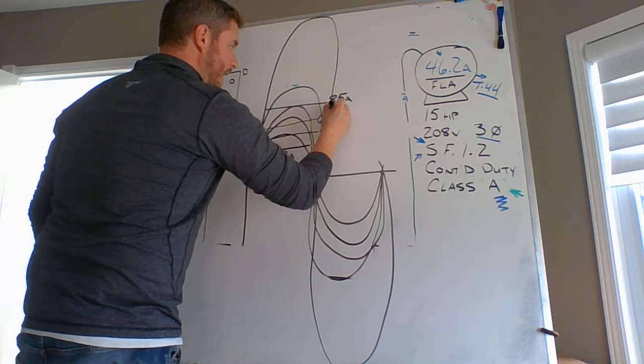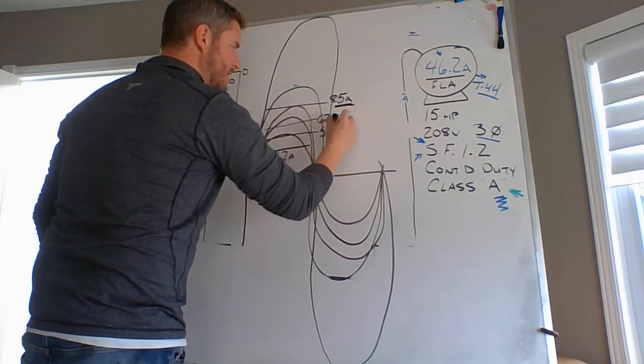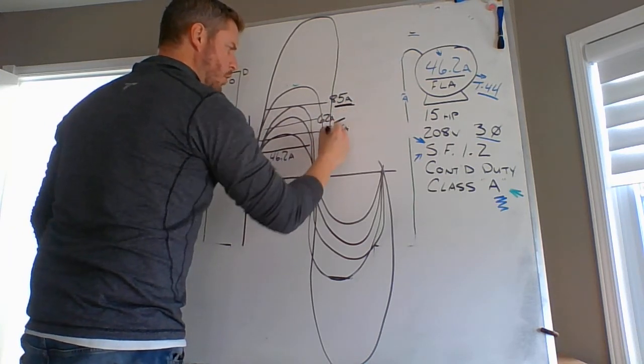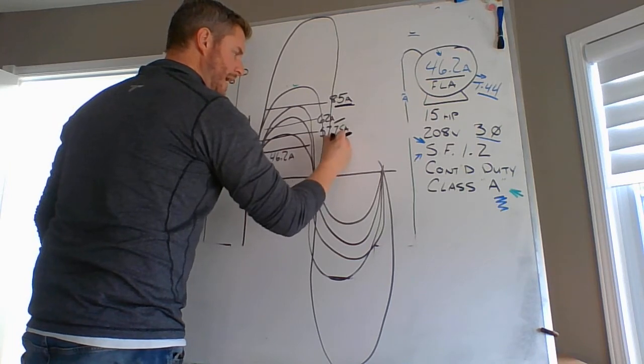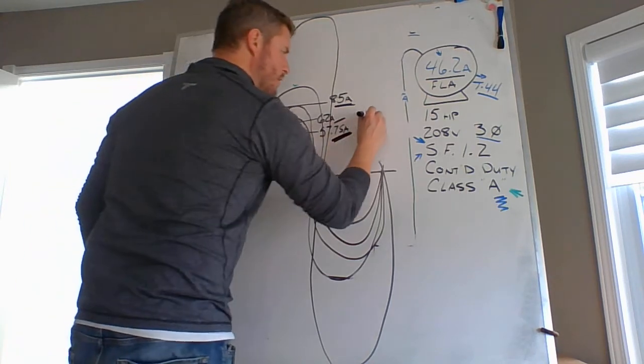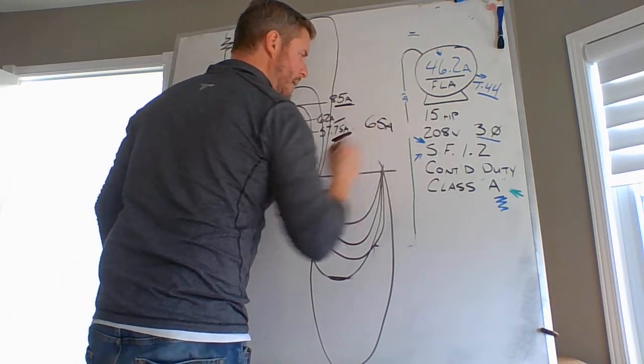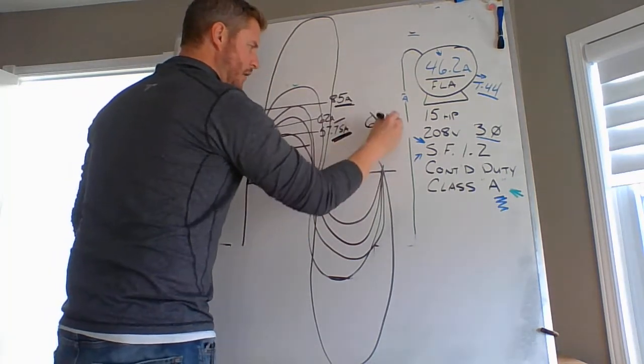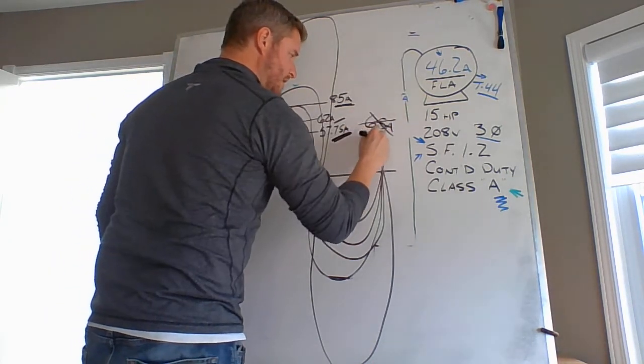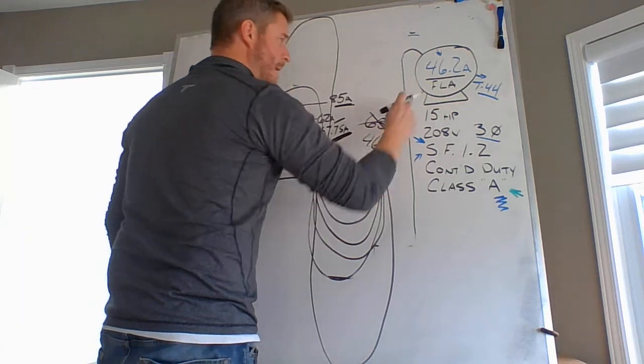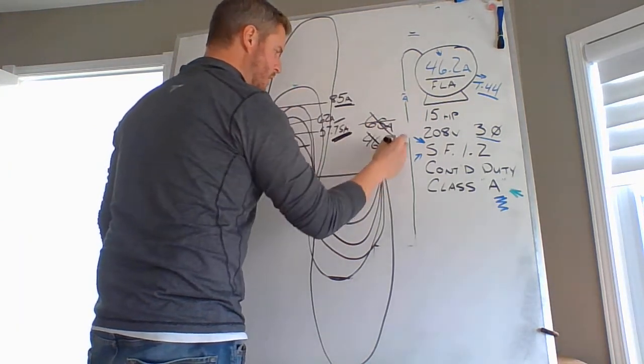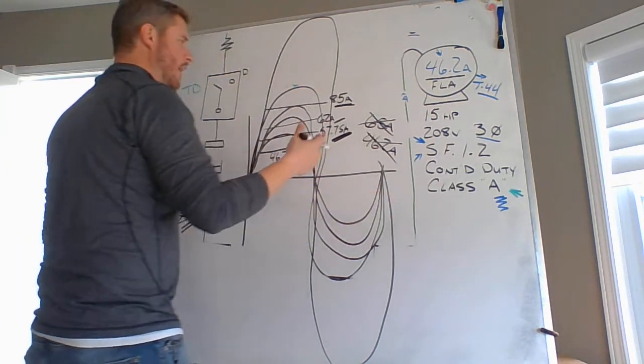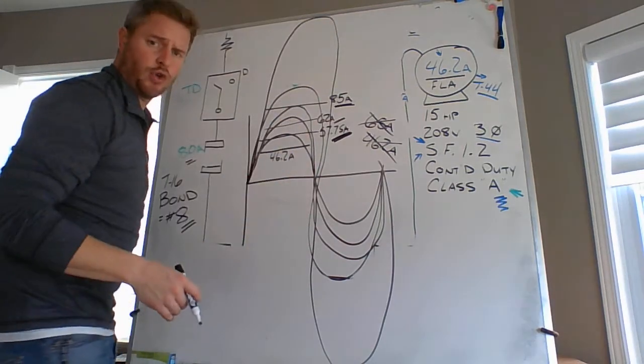So the 85 amp thing doesn't matter anymore. The 62 amp thing doesn't matter anymore. The 57.75 amp thing doesn't matter anymore. Or the 65 amp ampacity of your conductors, that doesn't matter anymore. Or the 46.2 amp maximum full load current rating of your motor doesn't matter anymore, because now you're drawing an exponential amount of current.